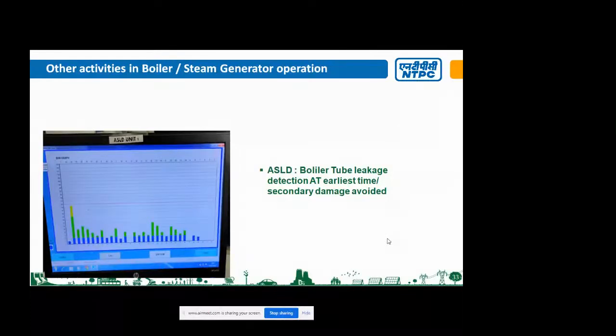Second, sir, we have fitted a furnace temperature monitoring system, an acoustic flame monitor. It gives the maximum temperature of the furnace and indicates any slagging or clinkering inside the furnace, so that we can take corrective action by operating AC/DC and air flow optimization.